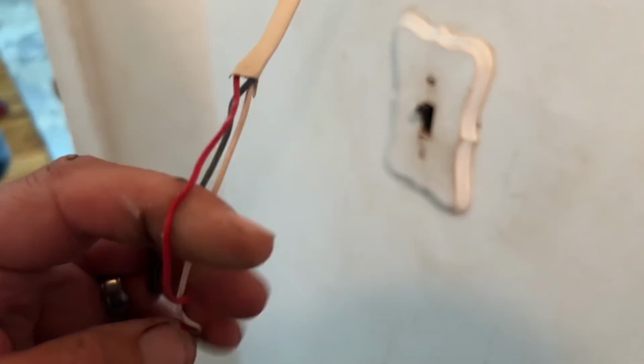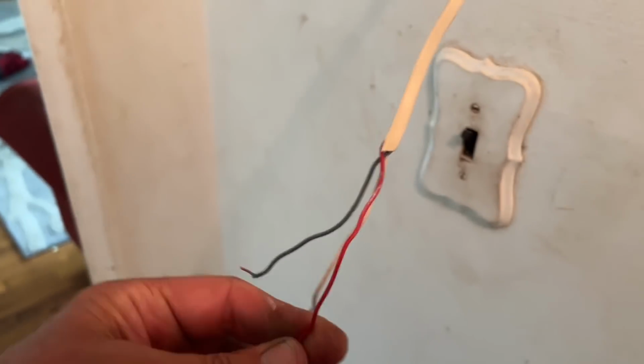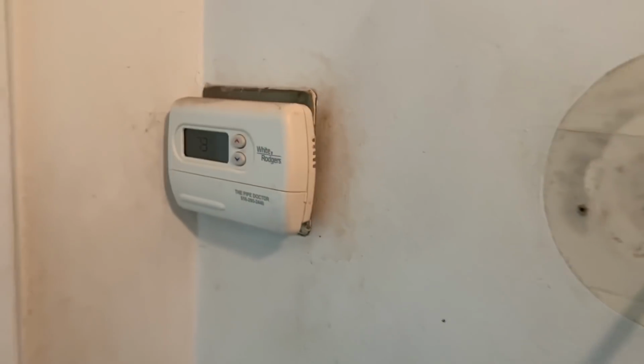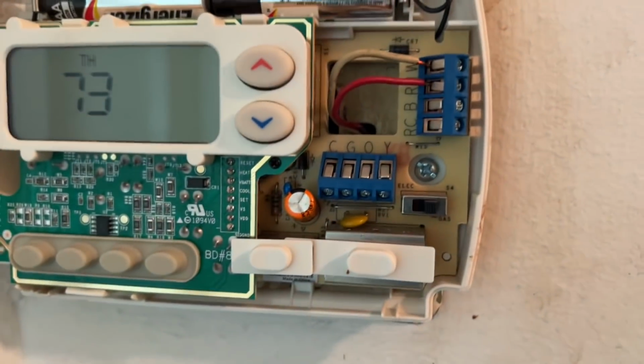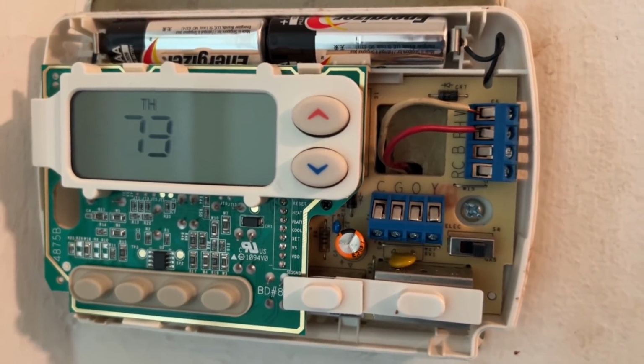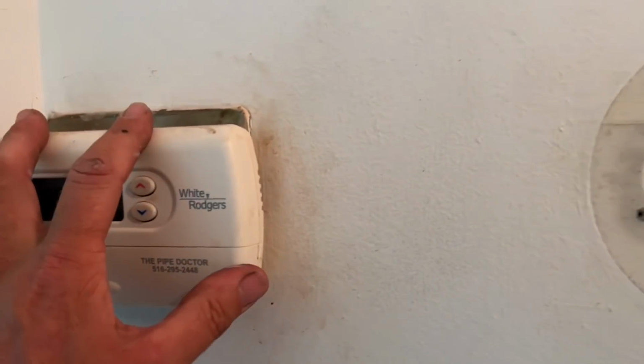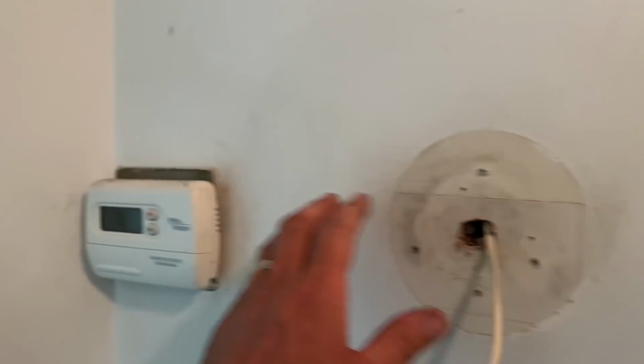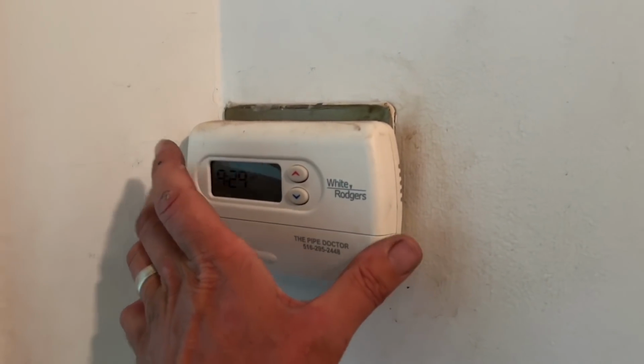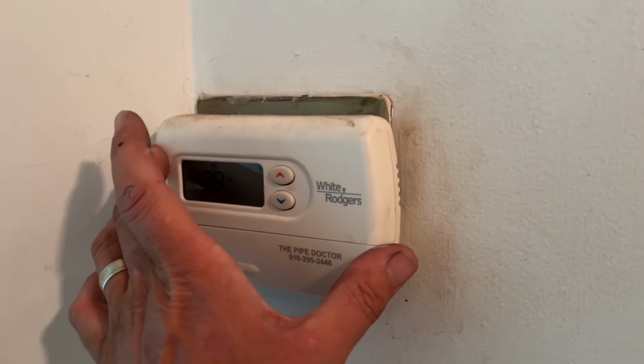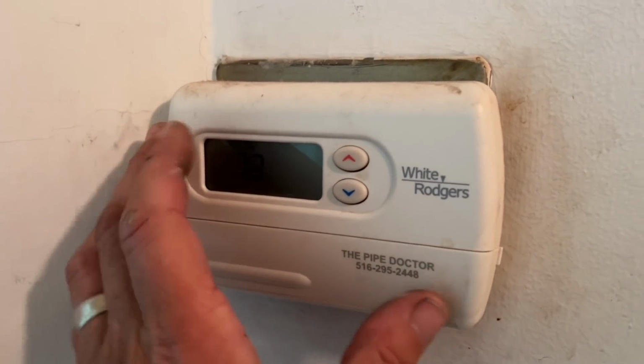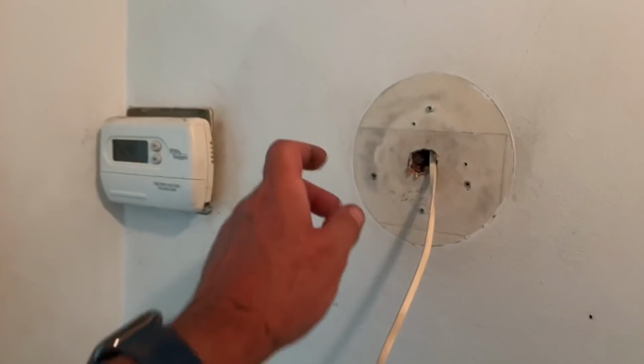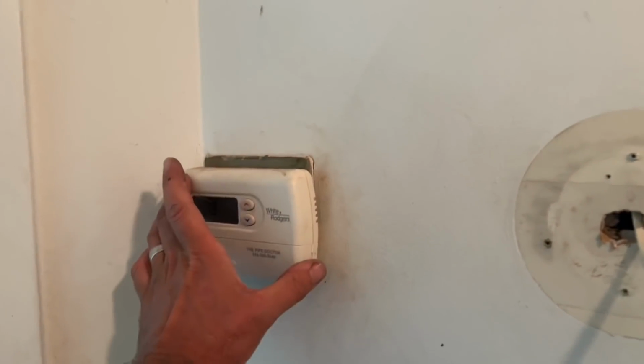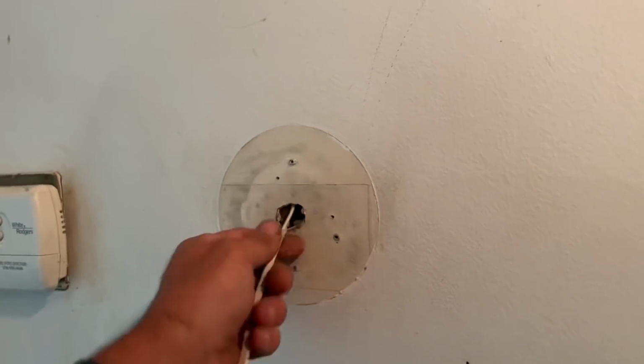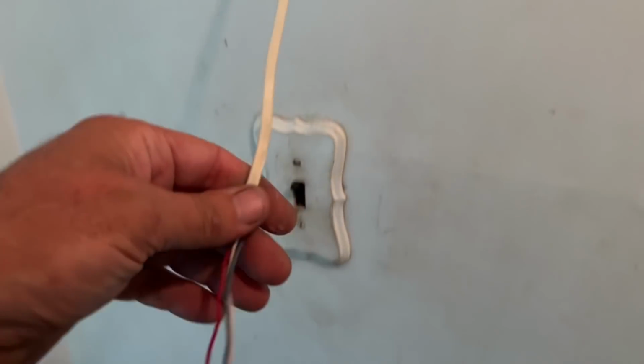So let's get some 5-wire and run new thermostat wire. It'd be nice if we could just tie it right into this thermostat here, one thermostat for both, but we're using the heat pump functionality of the Bosch. We're still going to maintain the oil for emergency heat on really cold days, if it ever gets to like -10 degrees that'll fire up. For domestic hot water we're still using oil, but for central heating and cooling we've got the Bosch.